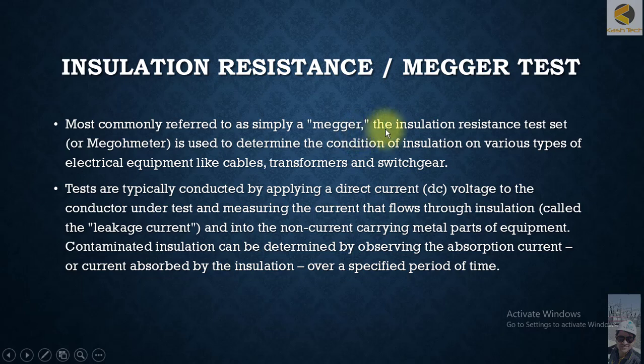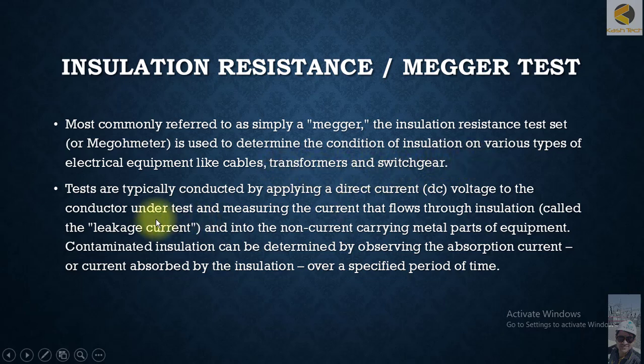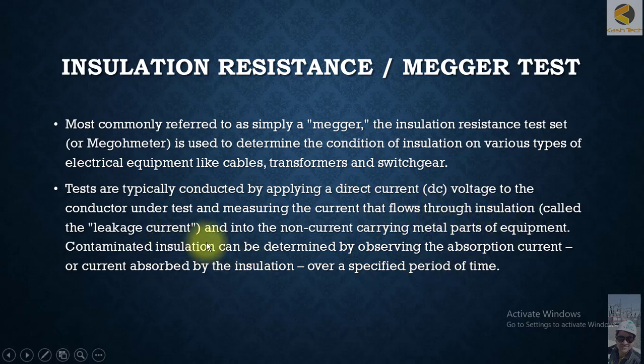Megger testing — most commonly referred to simply as mega testing — uses an insulation resistance tester or megohmmeter to determine the condition of insulation on various types of electrical equipment like cables, transformers, switchgear, etc. Tests are typically conducted by applying a direct current (DC) voltage to the conductor under test and measuring the current that flows through the insulation, called the leakage current.